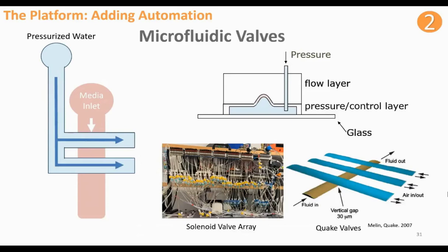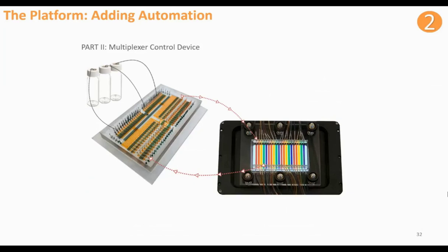However, with gel-based cell culture systems such as organoids, these valve-based systems would dramatically decrease our throughput and efficiency if used directly with the organoids. To prevent that, we developed a second device to control and automate our experiment: the multiplexer control device. This consists of a multiplex array of different valves that can control the movement of various solutions — our current device holds up to 30 different solutions — and can direct them to various channels dynamically in various timing.